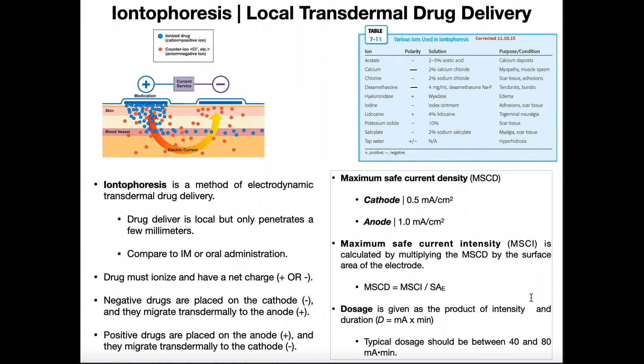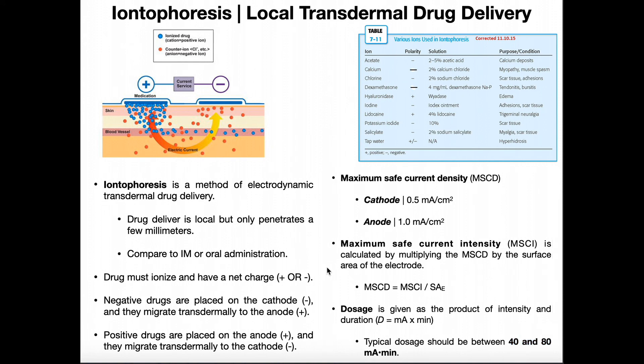We also have dosage. Dosage is the product of the intensity of the treatment in milliamps and the total duration of the treatment in minutes. Because we're multiplying milliamps times minutes, the units of dosage are milliamp-minutes. Usually the dosage should be between 40 and 80 milliamp-minutes.